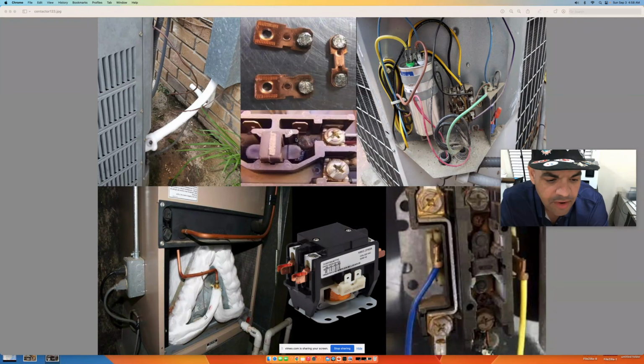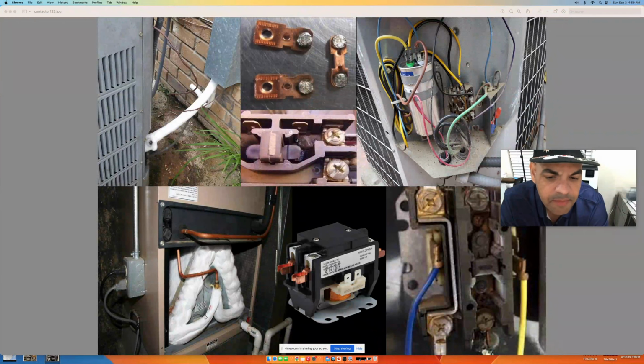Another way you can troubleshoot this is you can get a multimeter and check continuity across the actual contactor. So what you do is you just check if there's continuity from one side to the other side of your contactor, and that's how you can also check if your contactor is actually stuck with the multimeter. Now, like I said, keep in mind sometimes your contactor will look stuck or be stuck, but no voltage is going to get across. It looks like you should get voltage across, but if you do your continuity test with your meter, you're going to notice that you're not going to get voltage across to the other side of your contactor.